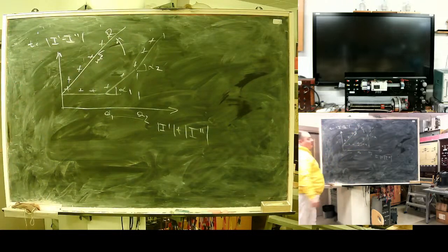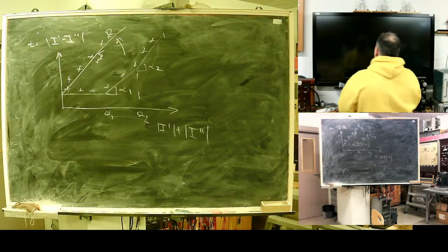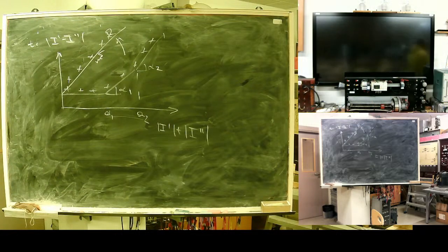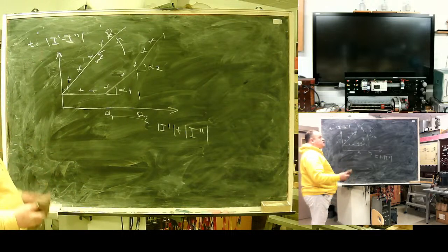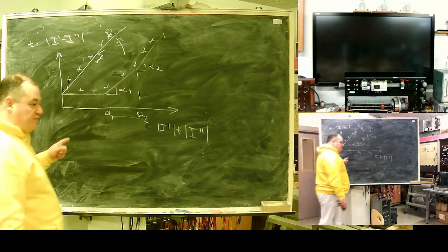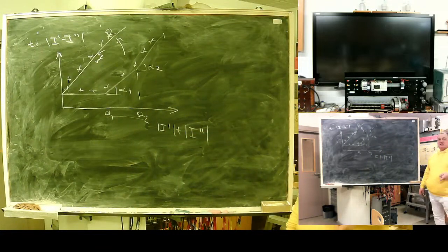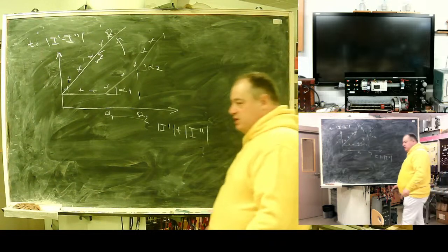So here the key moment is in data exchange. Also, what else? These protections are, of course, the most expensive, but if the exchange works, they offer us the best performance. They are faster, they are 100% selective, so it's the high end of line protection.